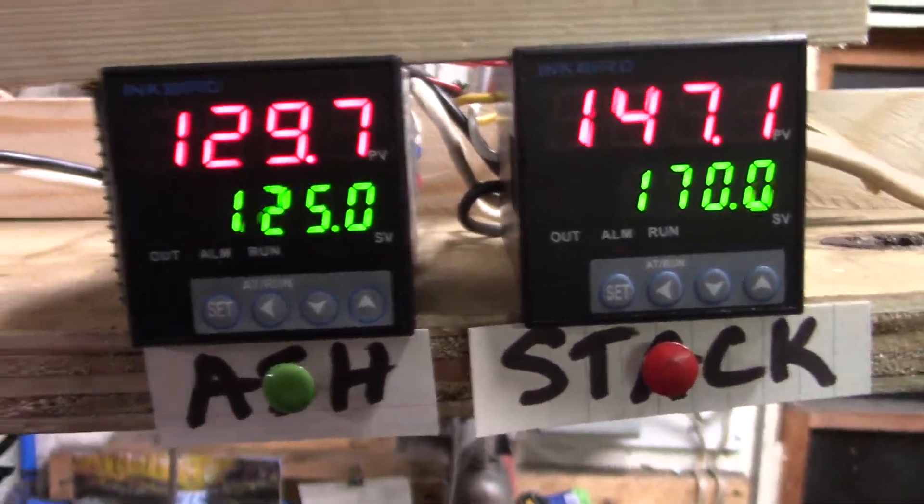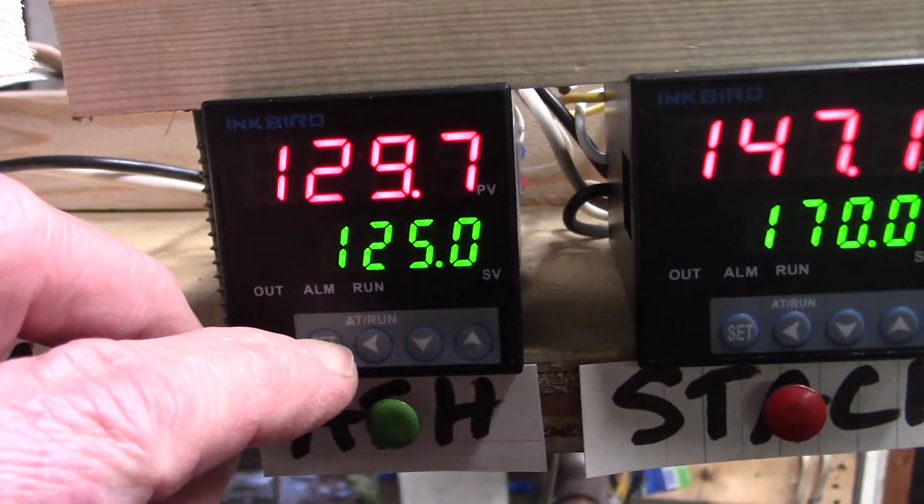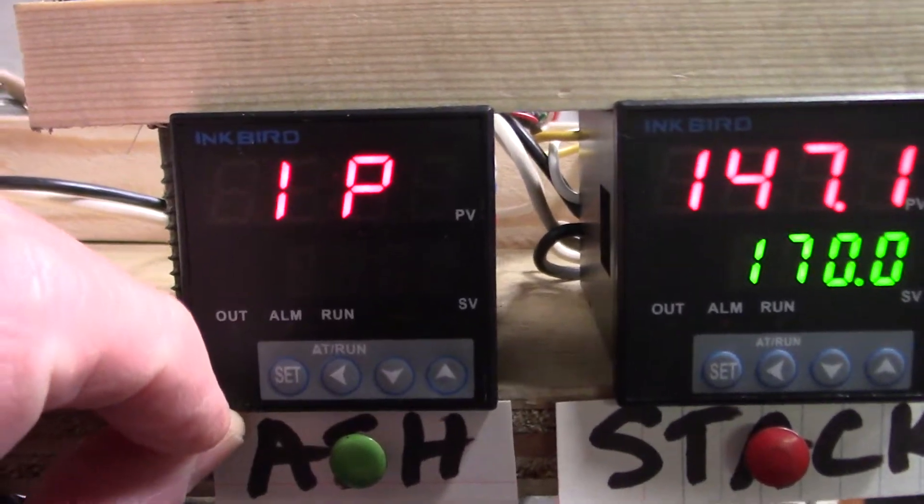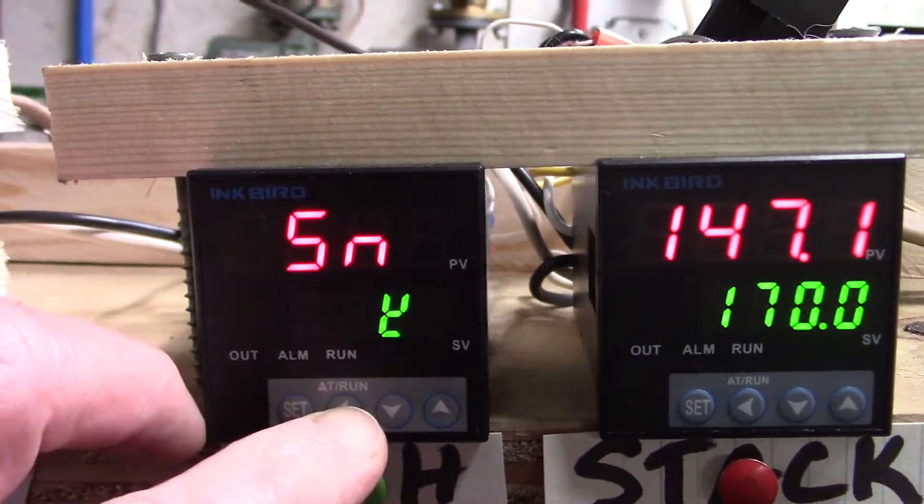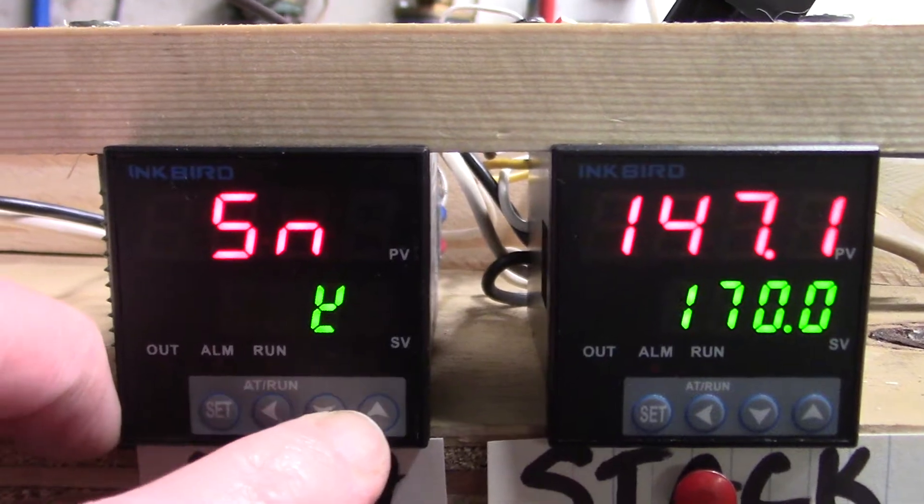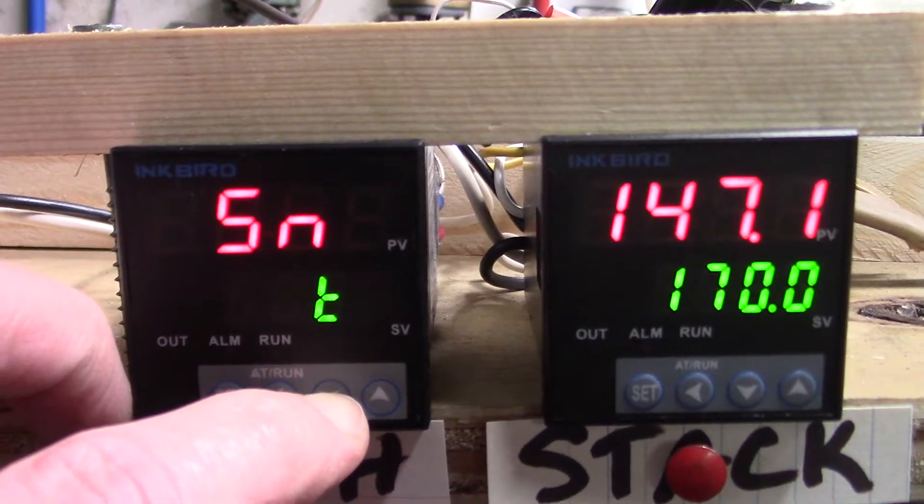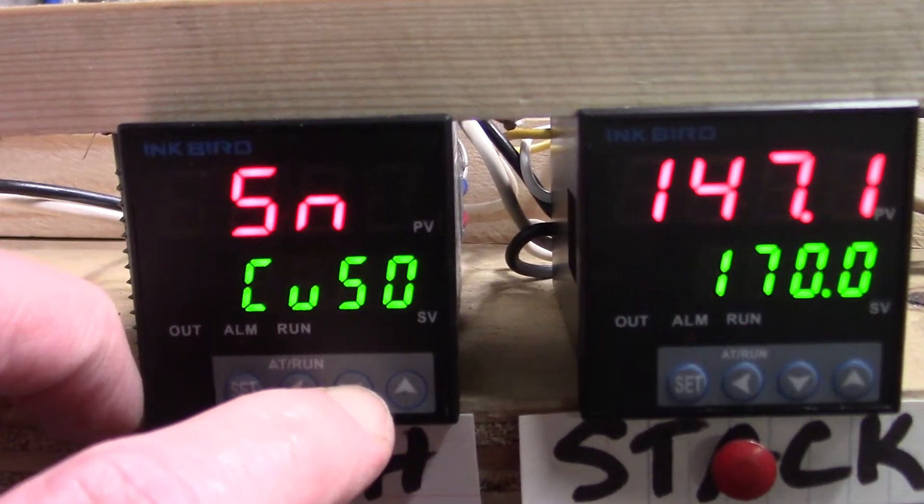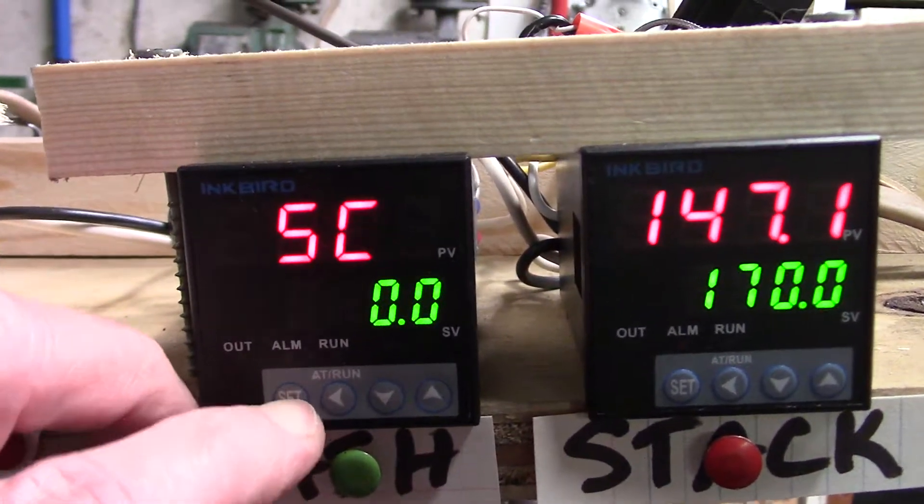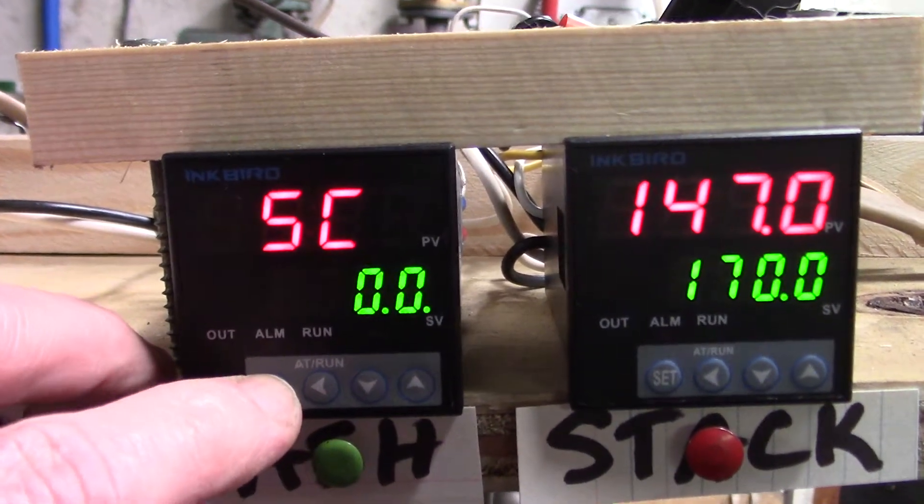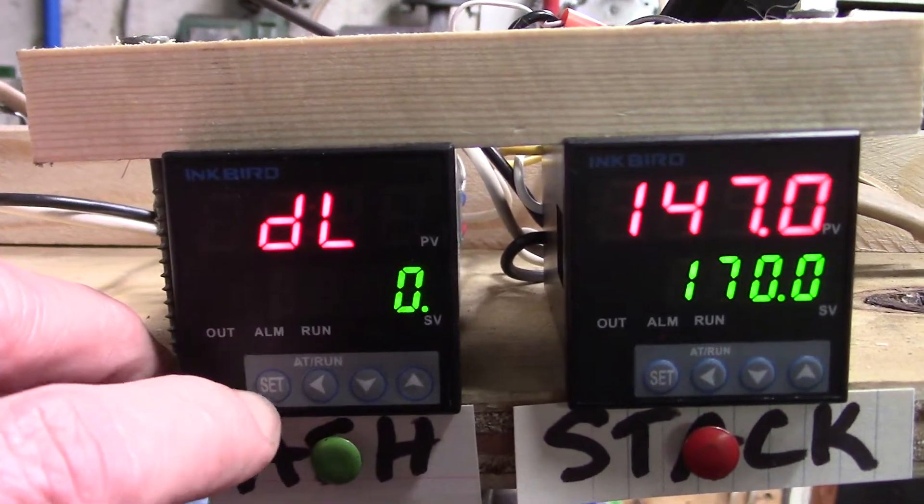So stand up here and look at this thing. To get into the menu we'll do the ashing one first. Hold the set button down for three seconds. Now you're in the IP menu. If you press the left arrow there you are, we're in Y which is a K thermocouple. You can change it, there's a chart in the instructions that tells you what means what, but we want Y.